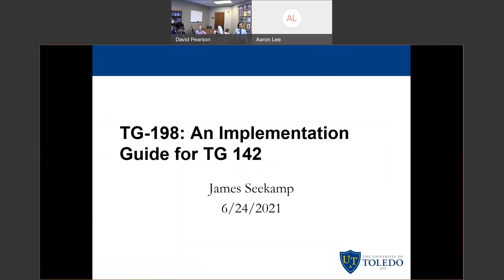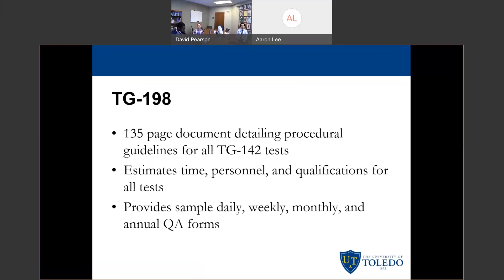We were talking about TG-198 and its implementation guide for TG-142. As we know, TG-142 is kind of the de facto law for what kind of quality assurance you have to do on your linear accelerators on a daily, weekly, monthly, and annual basis in many states. TG-198 has come out quite a bit later because it is very encompassing, and it was also being written at a time where treatment delivery was rapidly changing with things such as VMAT. It is a 135-page document as opposed to TG-142, which is about 14 pages.